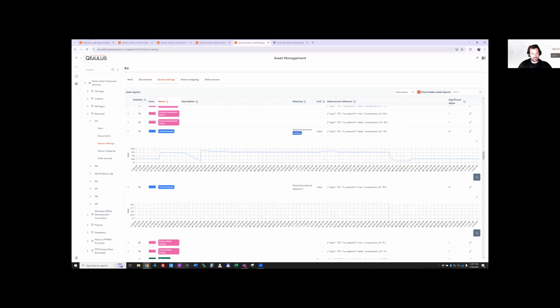Yep, that's exactly the point. And as Frank already said, QMULUS is directly, after each load, checking the health of these control loops, let's call it like that. And Frank already mentioned that we have three kinds of KPI we are calculating out of it. The one is the agility, the other one is the precision, and the last one is the accuracy. And having these three values in mind, we can check if the state or the behavior is moving in the right direction, or is it constant? Is it showing some outliers, and so on.